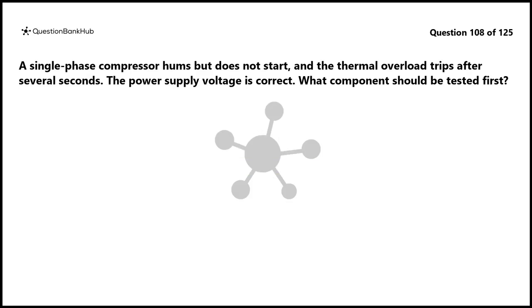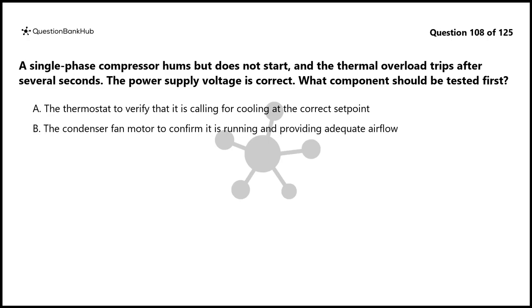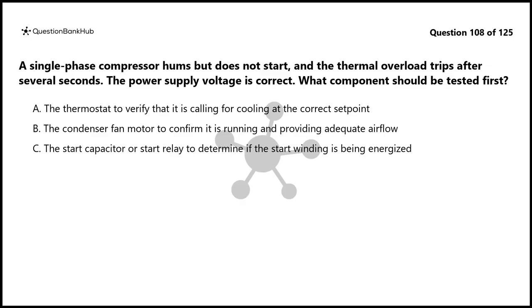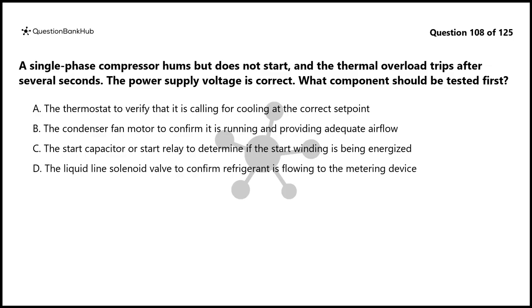Question 108. A single-phase compressor hums but does not start, and the thermal overload trips after several seconds. The power supply voltage is correct. What component should be tested first? A. The thermostat to verify that it is calling for cooling at the correct set point. B. The condenser fan motor to confirm it is running and providing adequate airflow. C. The start capacitor or start relay to determine if the start winding is being energized. D. The liquid line solenoid valve to confirm refrigerant is flowing to the metering device.